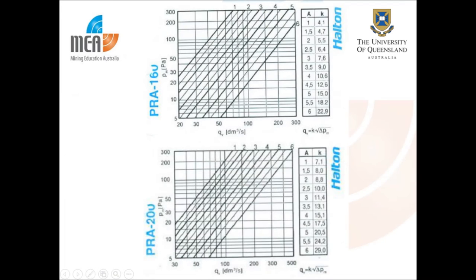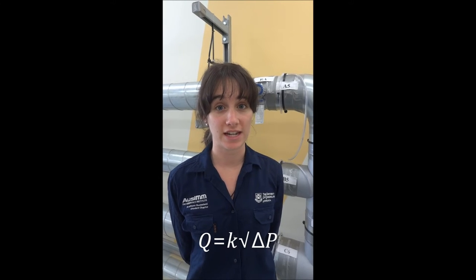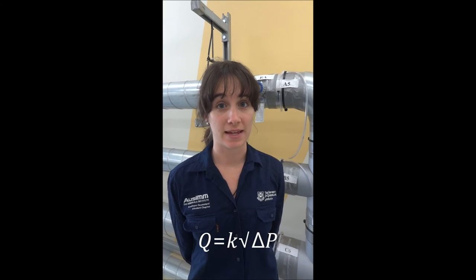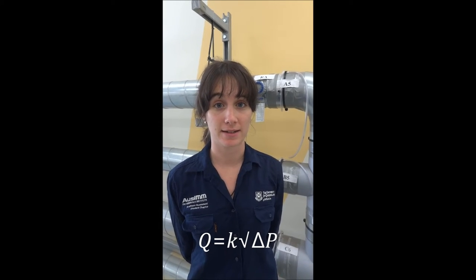The calibration coefficient for each regulator can be found from these tables — the top one for ducts A and B, and the bottom for duct C — using a given A value of 6. Recording the pressure change across the orifice plate and using the calibration coefficient k for each orifice plate, the quantity of each airway can be calculated from the equation displayed.